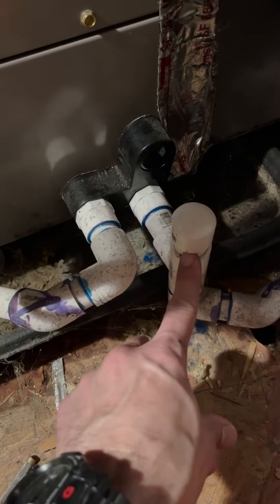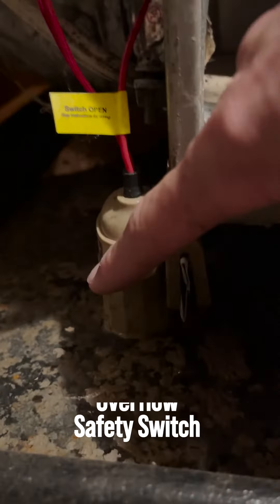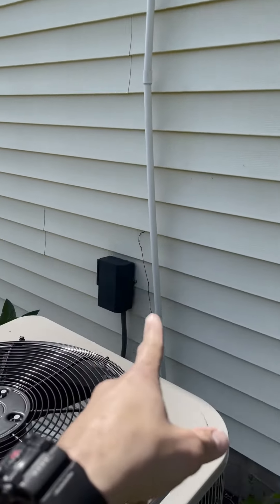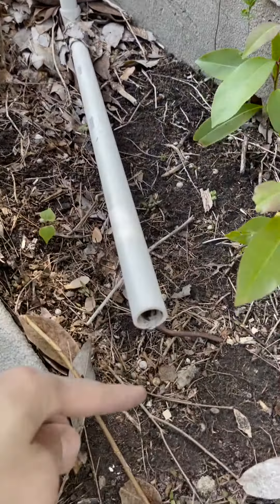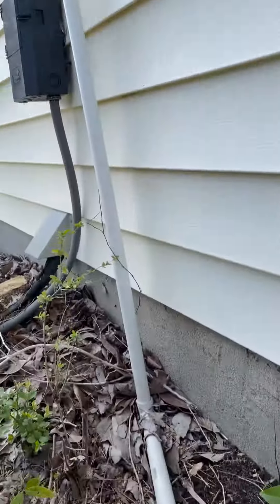You really want this to be draining primarily, because if this fills up your unit shuts off by this safety switch. But if you can clean this out — out there is the primary drain, comes over here and leads out here. You get a shop vac and just suck out all the gunk. Coming in here, this would help.